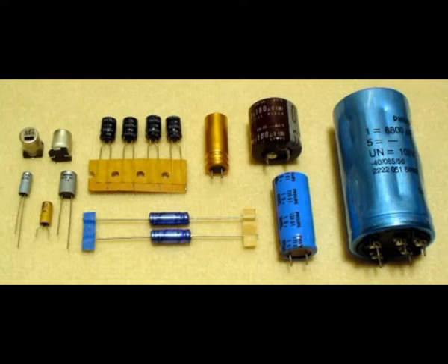Periodically appearing high current pulses, which may be much higher than the rated ripple current, have to be analyzed in the same manner. Because the ESR decreases with increasing frequencies, the ripple current data sheet value, specified at 100 and 120 Hz, can be higher at higher frequencies. In cases like this, manufacturers specify correction factors for ripple current values at higher frequencies. For example, the ripple current at 10 kHz can usually be approximated to be 30 to 40% higher than the 100 and 120 Hz value.